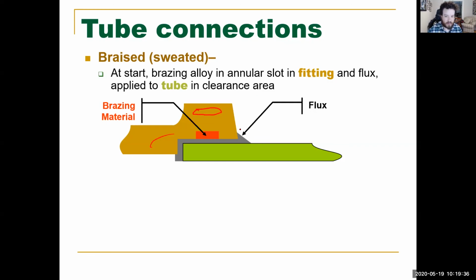And what it's designed to do is heat up and boil away when applying heat to it, all right? So when you heat it up, it boils away. And if you were to solder this instead of doing brazing, the solder is going to be added just where this arrow is right here. And when you're adding heat over here, this is going to be boiling up. So as the whole fitting is heating up, your piece of solder that's going onto this piece is going to flow into this cavity because it's going to create almost like a vacuum in here. And that's how you get a really nice solder connection.